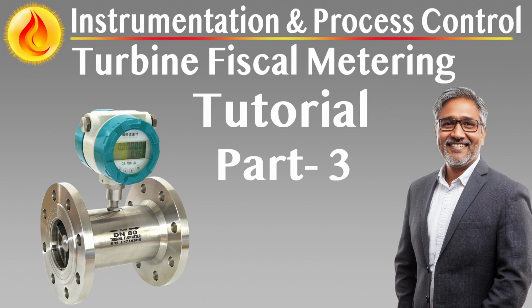A deviation between the 2 sensors beyond a specified threshold, typically 0.5 to 1.0 kilograms per cubic meter, must automatically trigger a system alarm and isolate the faulty measurement. The exact deviation limit is to be set based on process fluid characteristics and operational requirements. Signals from the densitometers must be transmitted digitally or as analog values to the metering microcomputers, where they are used to compute mass flow and to perform volume to mass conversions.